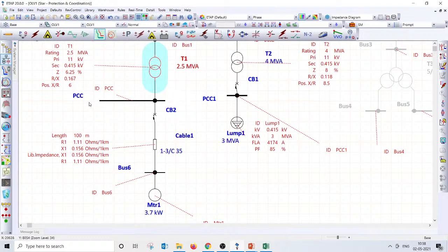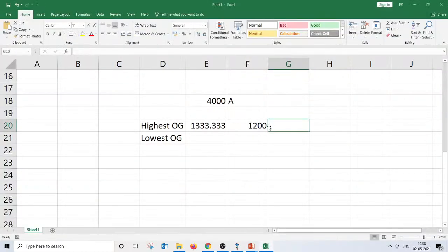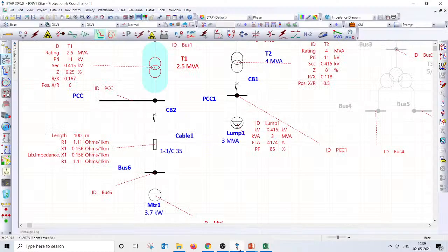So for the maximum outgoing, the ideal design, or the right way of designing, you should not go beyond 1200 amps for the feeder. Similarly, you should not go anything less than 250 amps. If needed you can go with maybe 160 amps, but if you are going anything less than 250 amps or 160 amps for an outgoing feeder, then the thing you need to really look at is your short circuit current withstand capability.